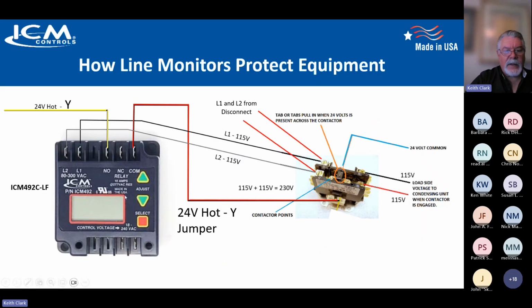Pretty simple. Here's just a little more real world look at the wiring. So your L1, L2 come from the disconnect right here, and then continue on. And then your Y call is going to get broken across here, and the device is going to determine whether or not to send power to the contactor and pull it in.